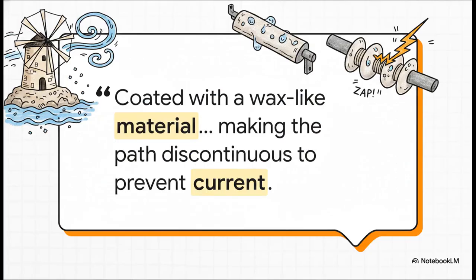It's wild. Or take the sheer ingenuity shown on the Greek island of Crete. Being an island, their power grid is constantly battered by fierce ocean winds carrying highly conductive sea salt. It was causing constant flashovers and required non-stop cleaning. So, to combat this aggressive sea salt pollution, engineers started coating the insulators in a specialized, highly water-repellent wax. This wax forces any salty moisture to bead up into isolated droplets rather than forming that dangerous, continuous conductive sheet we talked about earlier. This simple chemical intervention broke the electrical path on a molecular level, drastically reducing outages and saving massive amounts of money on constant washing.